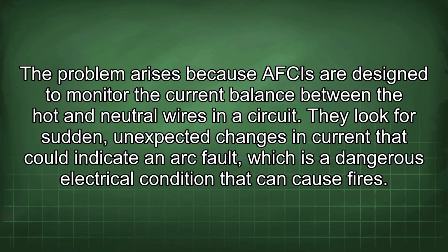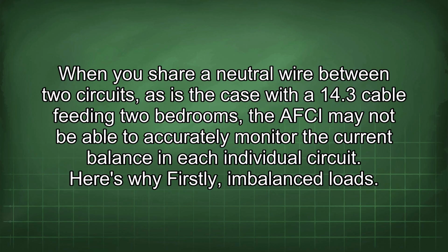The problem arises because AFCIs are designed to monitor the current balance between the hot and neutral wires in the circuit. They look for sudden, unexpected changes in current that could indicate an arc fault, which is a dangerous electrical condition that can cause fires. When you share a neutral wire between 2 circuits, as is the case with a 14/3 cable feeding 2 bedrooms, the AFCI may not be able to accurately monitor the current balance in each individual circuit.